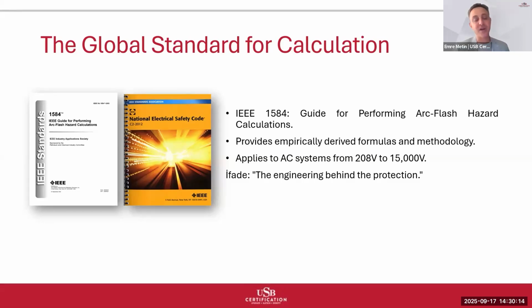What makes the IEEE standard particularly valuable is that it's based on real test data, not just theoretical modeling. Researchers created hundreds of arc flash events under controlled conditions, measuring actual incident energy levels at various distances and system configurations. The standard provides empirically derived formulas that apply to AC systems from 208 volts up to 15,000 volts, covering the vast majority of industrial and commercial electrical systems. These formulas account for factors like system voltage and available fault current, conductor spacing and enclosure type, working distance from potential arc location, protective device characteristics, and clearing times.